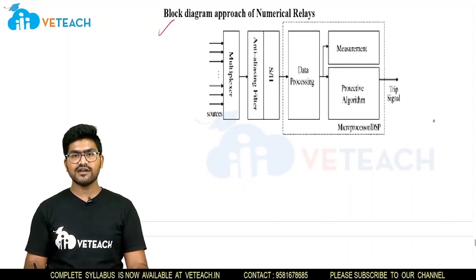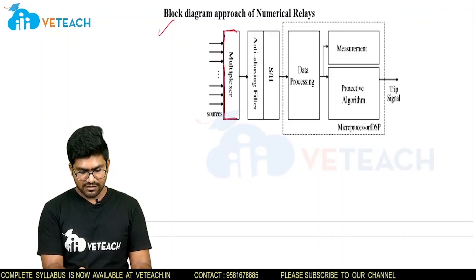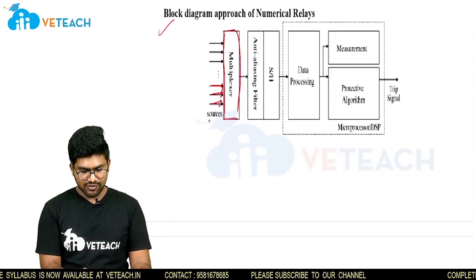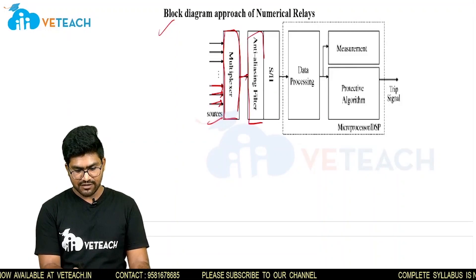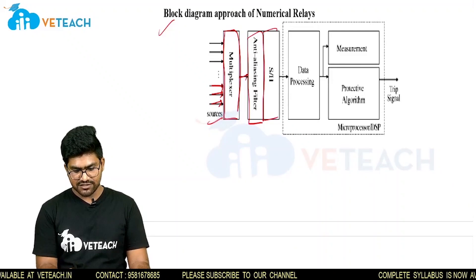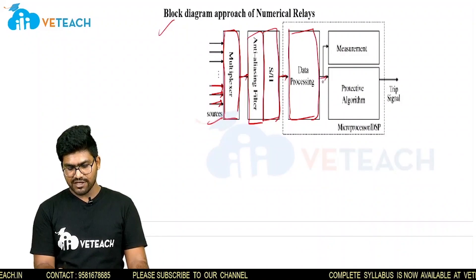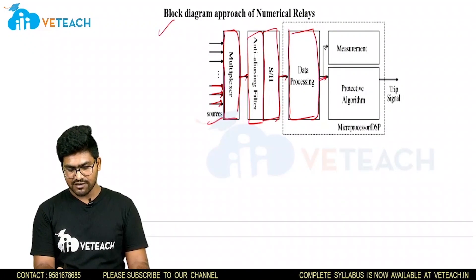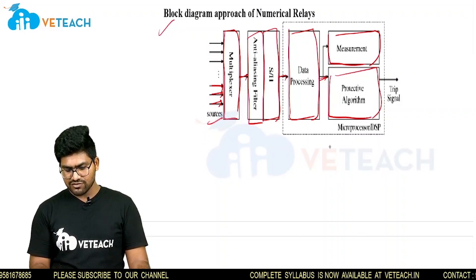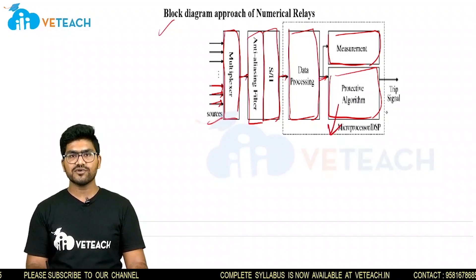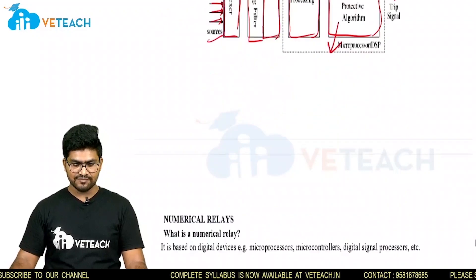Coming to the block diagram approach of numerical relays. From here we have taken a multiplexer, to which inputs from sources are given. The output of the multiplexer is connected to an anti-aliasing filter, then to a sample and hold circuit, and this is connected to a data processing unit. The output of the data processing unit is connected to the measuring element — the measurement and protective algorithm. This protective algorithm is essentially the microprocessor. The output of this protective algorithm is given to the trip signal.